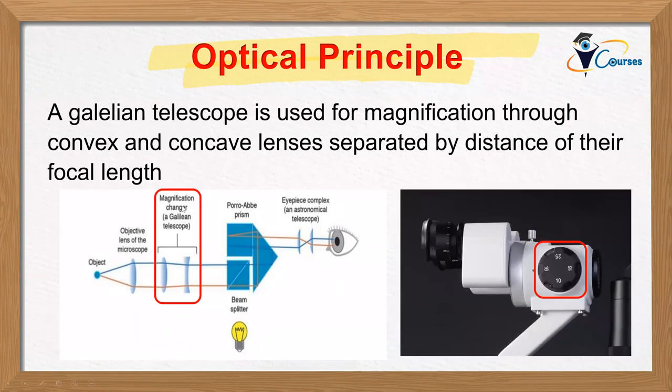Then we have the magnification changer. It is a Galilean telescope that has a plus lens and a minus lens separated by the distance of their focal lengths. By changing this knob, you are changing different sets of Galilean telescopic lenses of plus and minus lenses, leading to increasing and decreasing the magnification. So the basis of magnification here is this Galilean telescopic system, which is a very important advantage of the slit lamp.